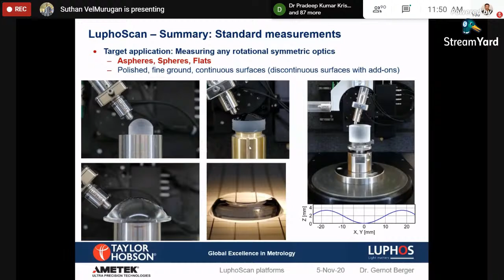And I have some statistical data on how accurately we can measure. We had a 25 millimeter diameter test calibrated sample, which was calibrated in an internationally traceable laboratory, the US laboratory. We tested almost 5 times, taking the part out and putting it back, and measured it. You can see the difference across the 5 measurements is just 0.7 nanometer RMS, which is less than 1 nanometer. And the PV 99 and power are the parameters which customers are mostly interested in. PV 99 is one of the very tricky parameters, and all customers measure it. In all 5 measurements, the result is less than 3 nanometers.